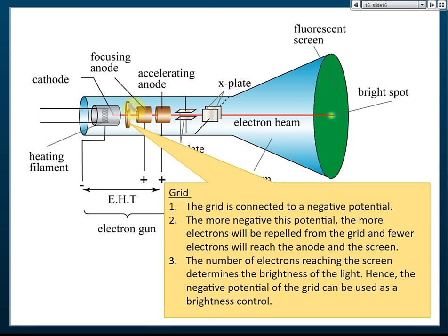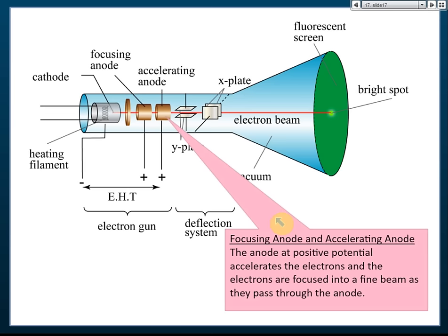In front of the cathode is a ring called the control grid. The grid is connected to a negative potential, which repels electrons. This controls the amount of electrons that can pass through it, and therefore controls the brightness of the spot on the screen. More electrons passing through produces a brighter spot; fewer electrons produces a dimmer spot. Hence, the negative potential of the grid is used as a brightness control.